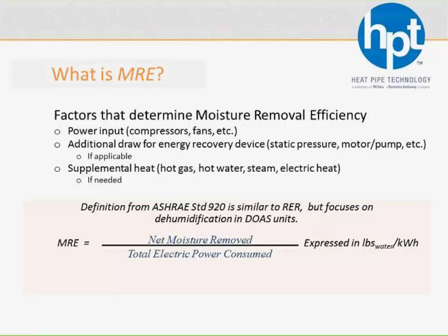So every DOAS unit is going to have an MRC, or moisture removal capacity, telling you how many pounds of water per hour, based on how many grains are coming in versus how many grains have been removed by the system. But more importantly, how efficiently it's doing it. And that kW draw is based on compressors, fans, static pressure, and even if there's supplemental heat like hot gas or hot water, all of that gets included to figure out how much power is needed for this DOAS unit to remove so much moisture.